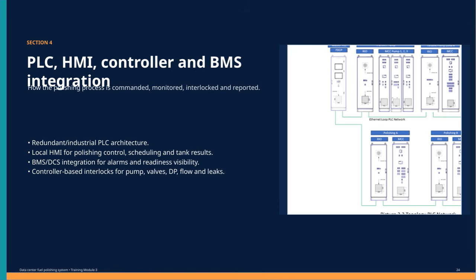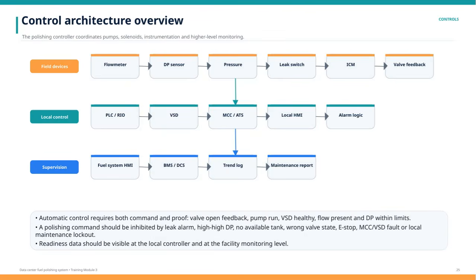Finally, controller-based interlocks are in place for critical components like pumps, valves, differential pressure, flow, and leak detection. These interlocks ensure the process operates safely by preventing potentially damaging conditions. This comprehensive integration makes the fuel polishing system efficient, safe, and transparent for operators and facility managers alike. Here, we have an overview of the control architecture for the polishing system.